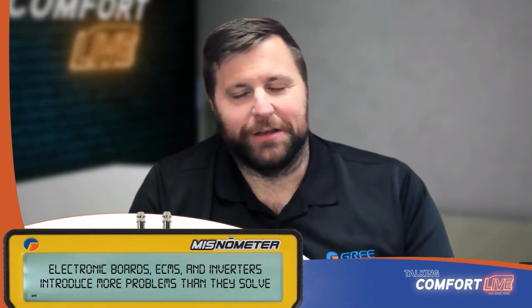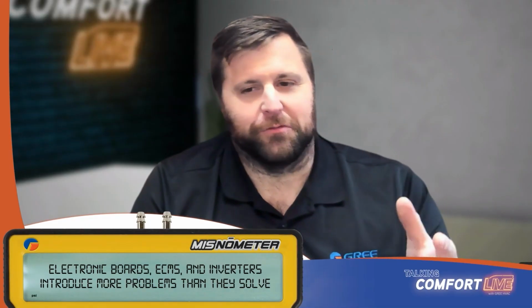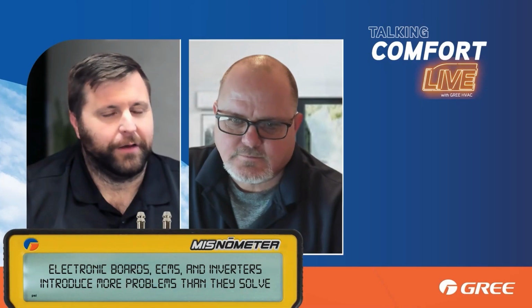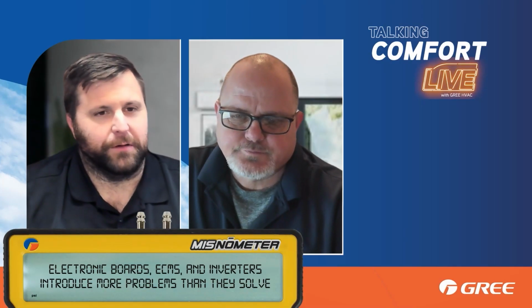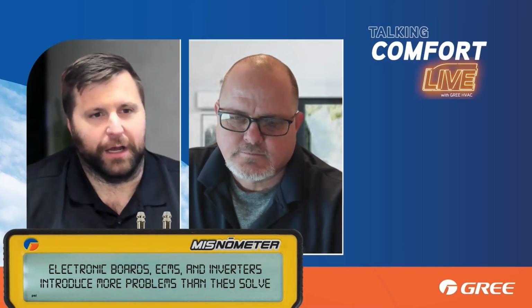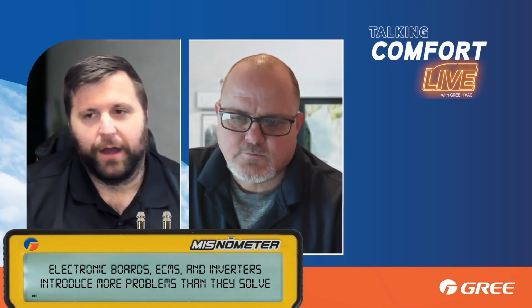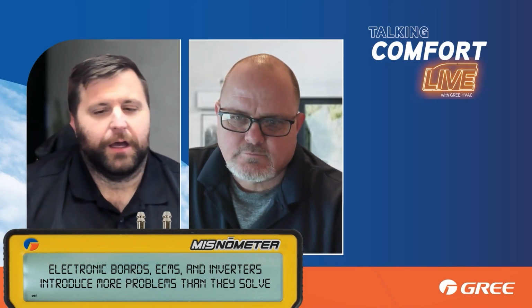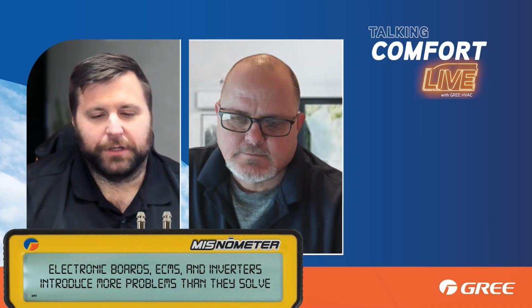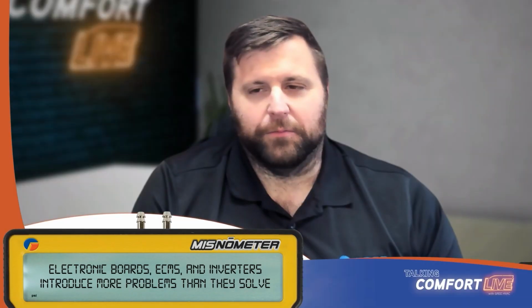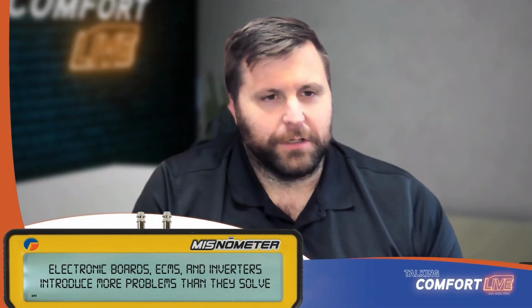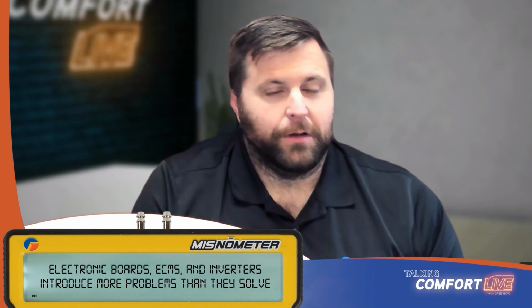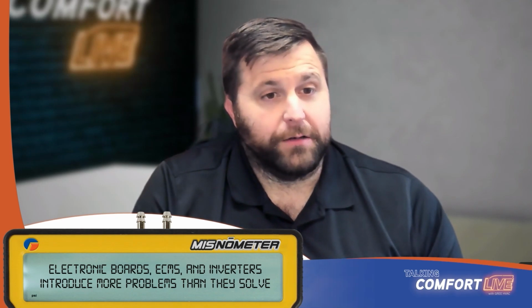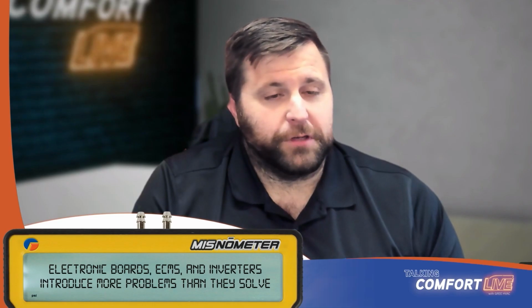I tell you what, there's a brand right now. I'm not going to mention any names or anything, but there's a very high dollar, high end inverter driven system that's out there. Really nice controller. I mean, top of the line, absolutely cool, right? I don't have a problem with it. Totally get it. But they did see a spike in inverter board failures, and as it turns out, your inverter board stays hot for a little while after it stops cooling.